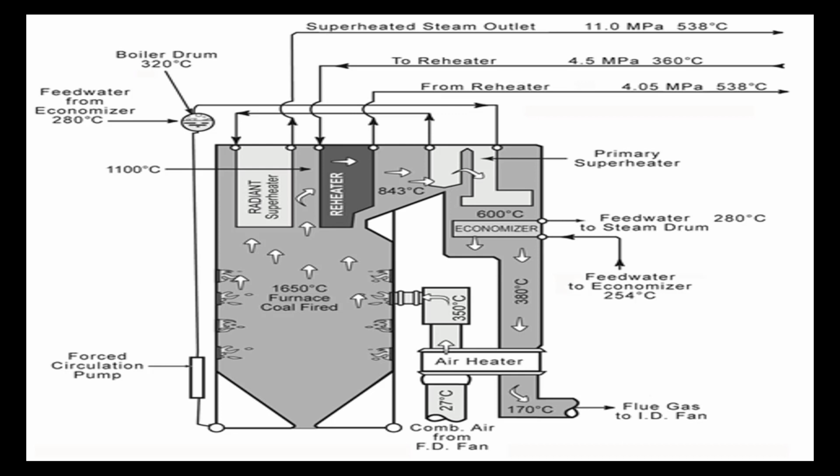So we're above the point here of thermal NOx being generated, and that's why a lot of these boilers have either SCR or SNCR systems fitted to remove the NOx. Other temperatures that they like to ask about are our stack temperatures, 170 degrees C typically in the stack, the air exit temperature from our air preheater, 350 degrees C. Then they of course like to ask about the reheat and superheat steam temperatures, and they are both the same at 538 degrees C.